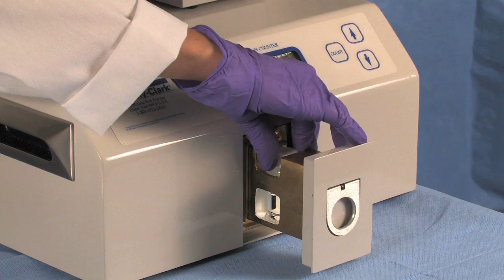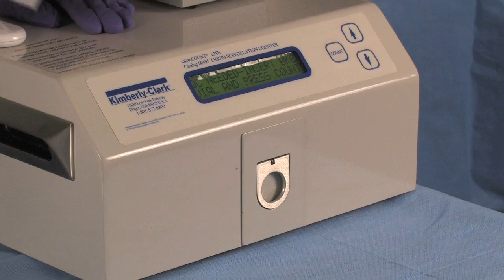If the standard set has expired, the DPM value, or disintegrations per minute value, will not calibrate your machine. Now, to put the sample in for counting after you've run your QC check, simply place the sample in the door, close it, and start your count. The count will be for 5 minutes.